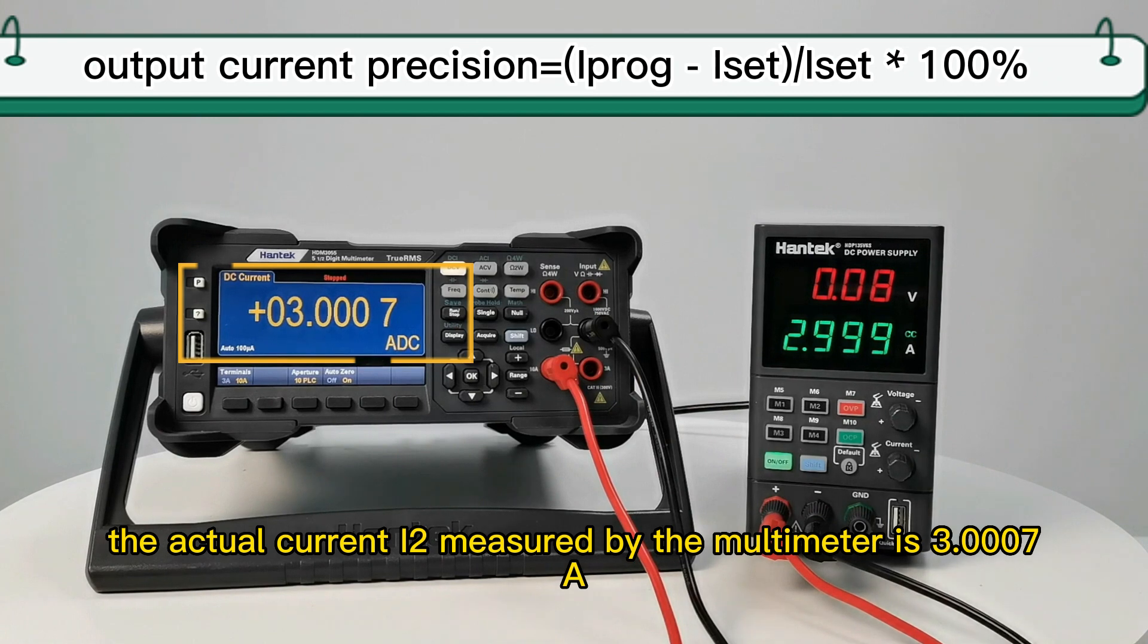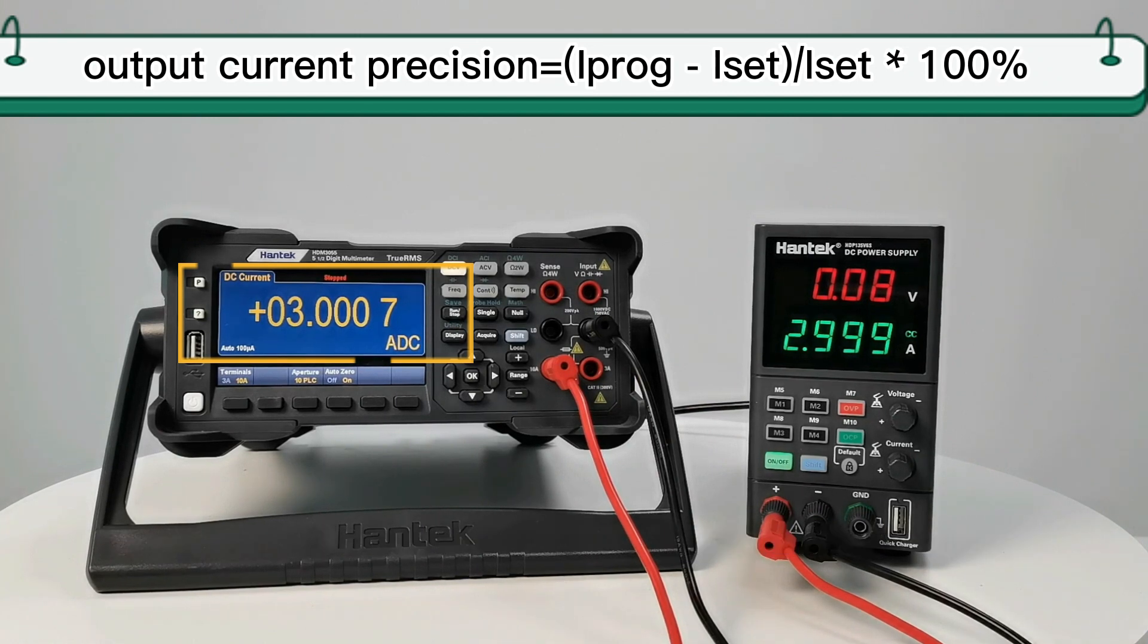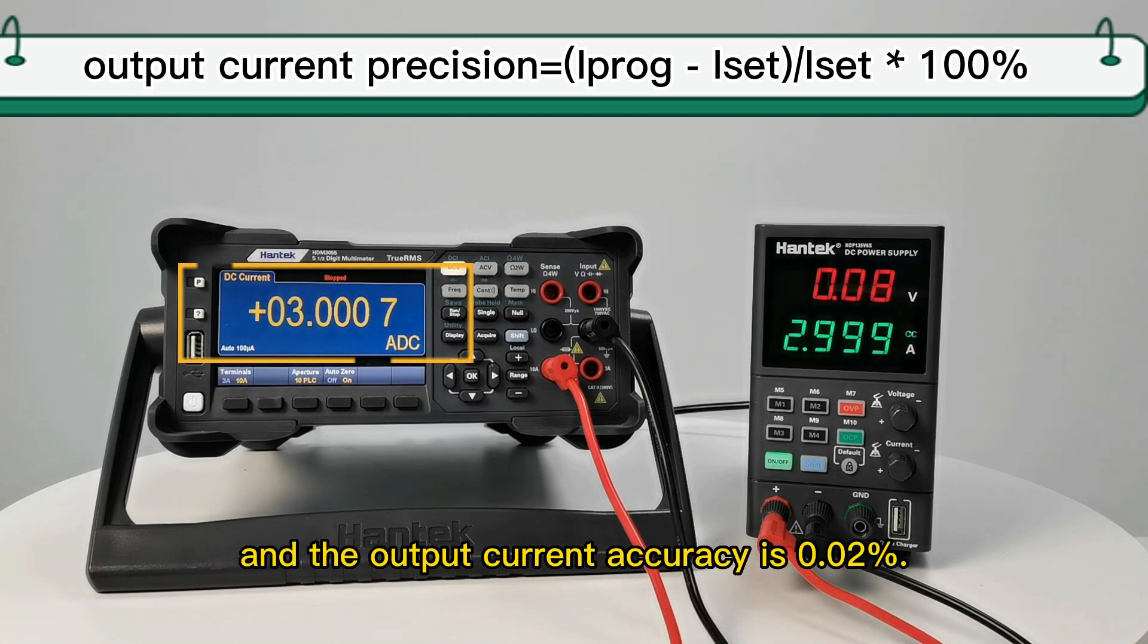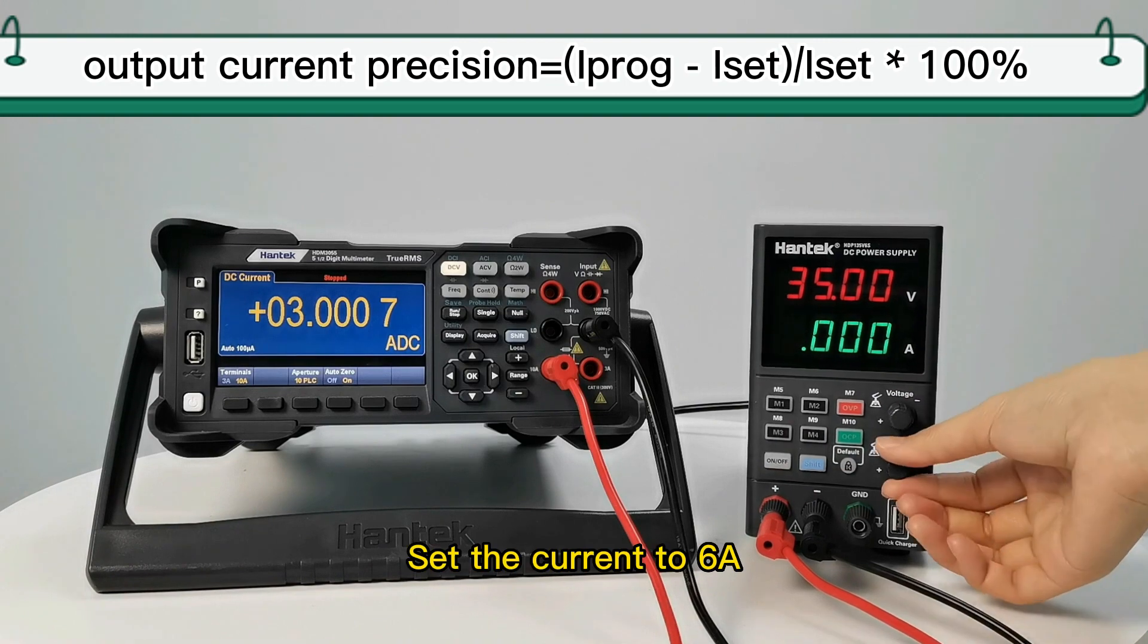The actual current I2 measured by the multimeter is 3.0007A, which is brought into the formula. The output current accuracy is 0.02%. Set the current to 6A.